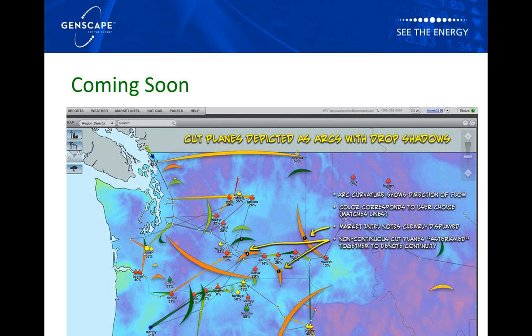So if there is an event where the flow either reverses direction or changes by a significant amount, that monitor will call up and send a data point in immediately. So under very normal conditions, you'll see about every 30-minute intervals on the readings. If things start to get exciting on that line, you'll get more frequent readings.